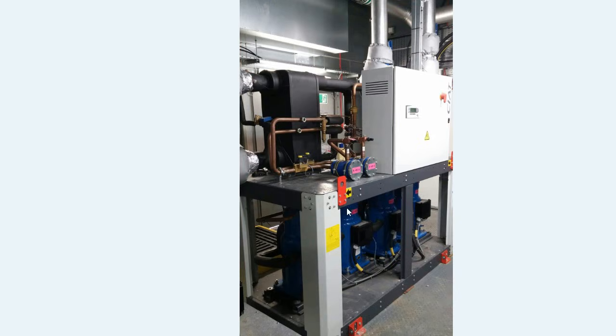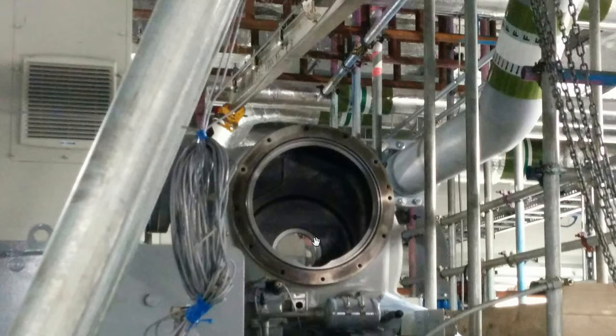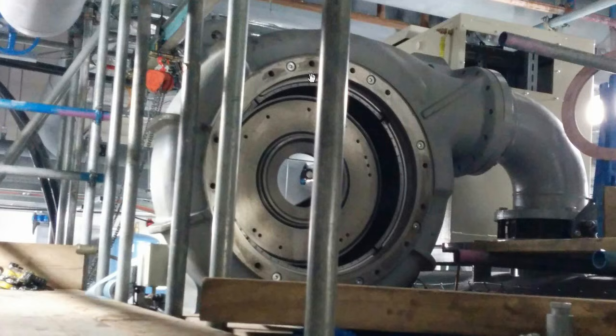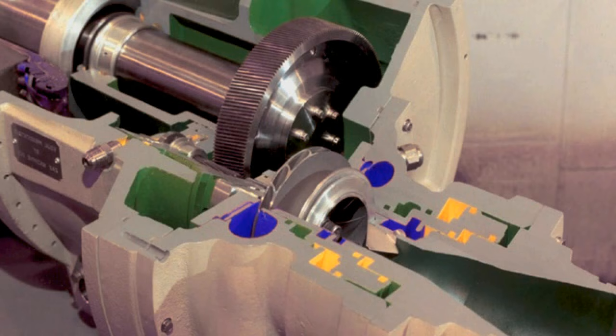It's not using centrifugal force, but just to give you an example of how small chillers are and how big they are really. You can also see here where one of our chillers was stripped apart, and you can see inside the actual chambers here. So the front view here, so you can see inside the volute as it's going, it would flow through and down into the discharge line. And there's also a section view here of the inside of the compressor unit.